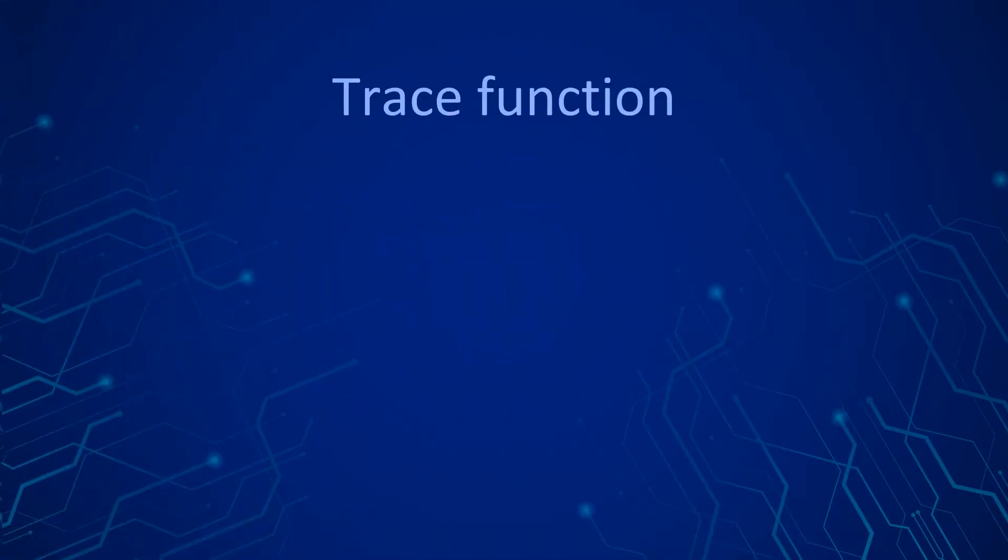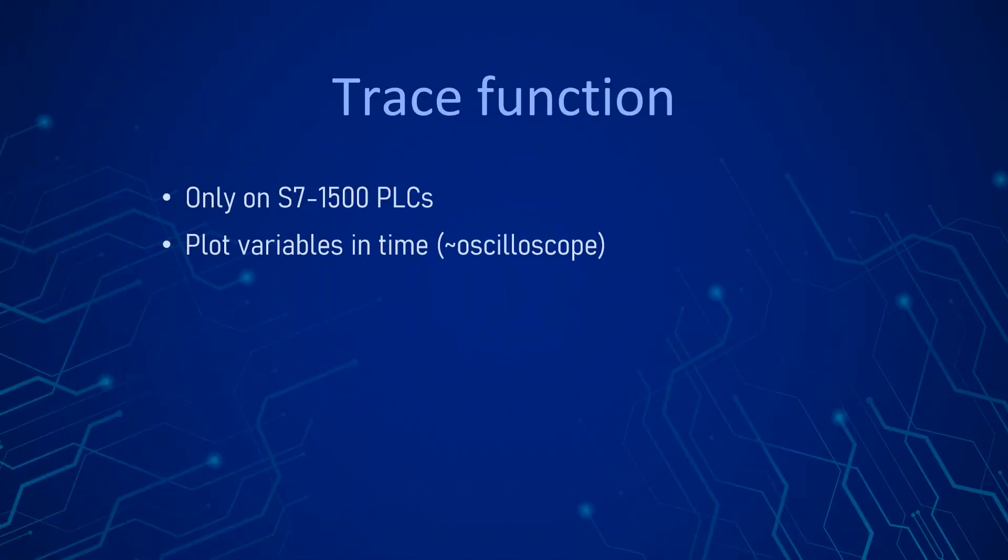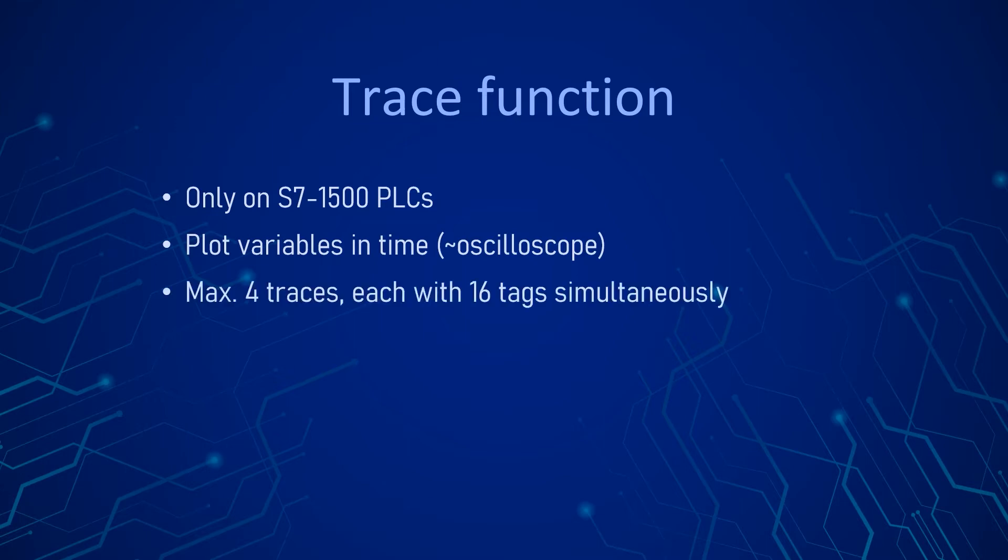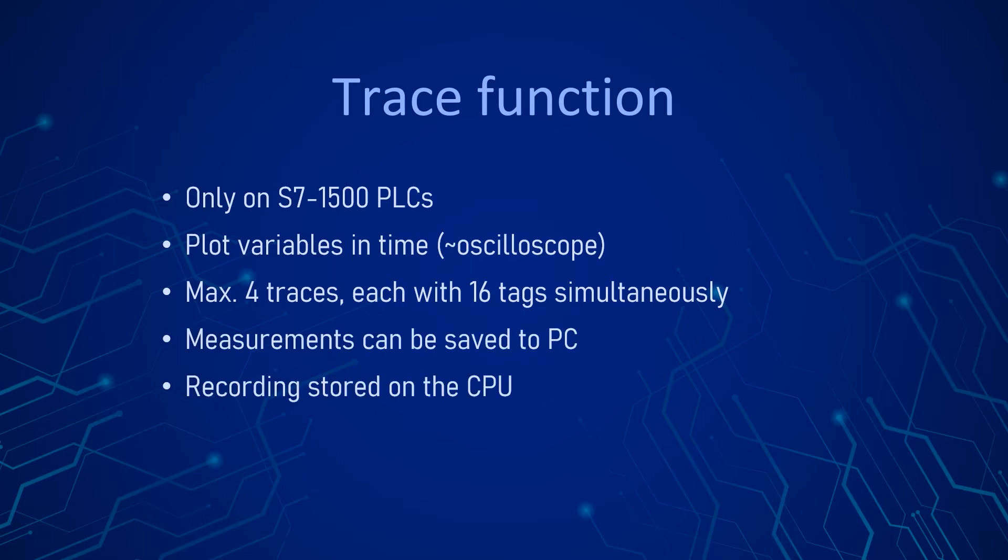The trace function is basically an oscilloscope for the variables in a PLC. With the help of the trace we are able to record tags value in chronological order. The recordings are stored in the system memory of the CPU. The trace configuration is retained after a power off, but the previously recorded data is lost.